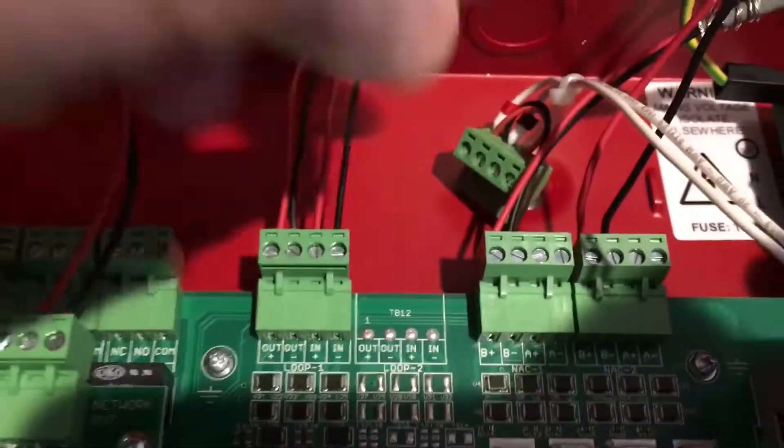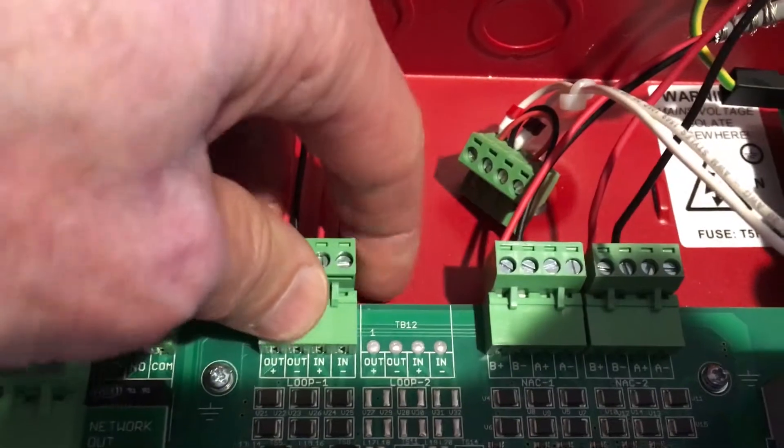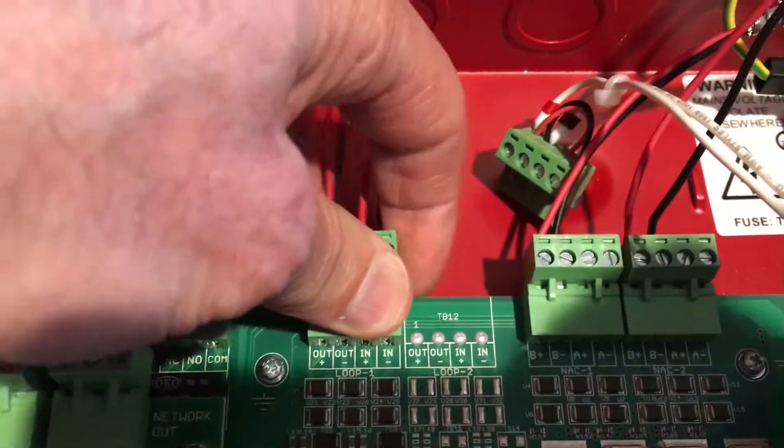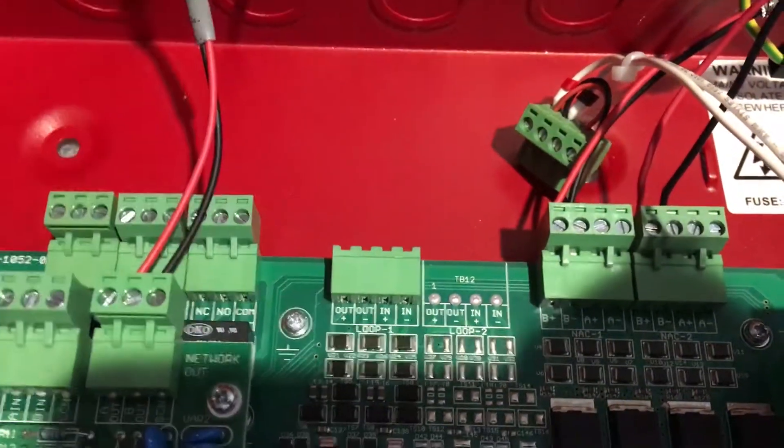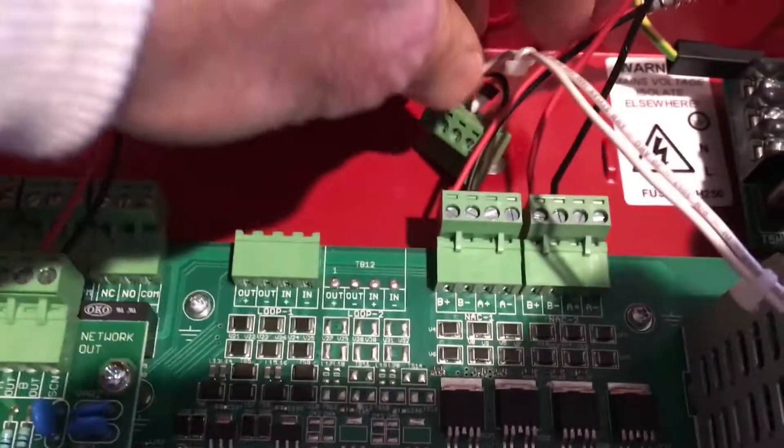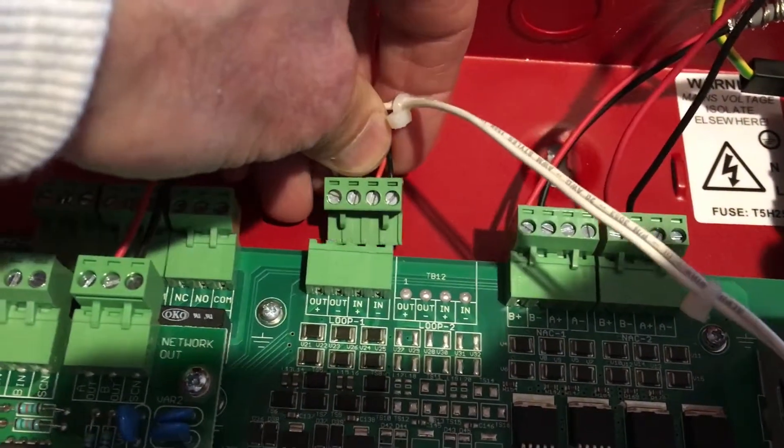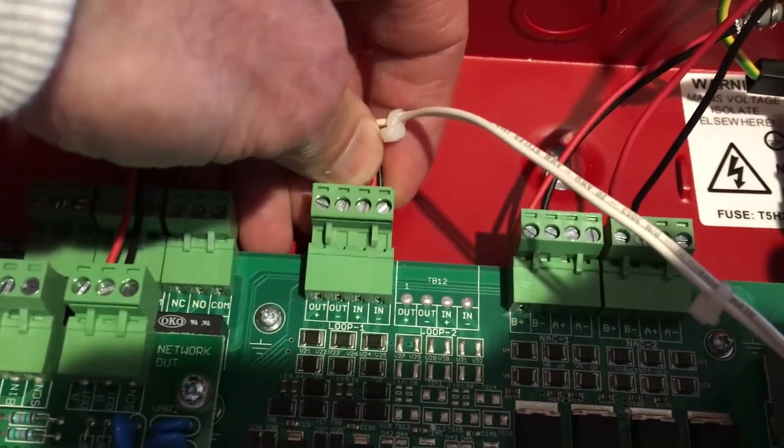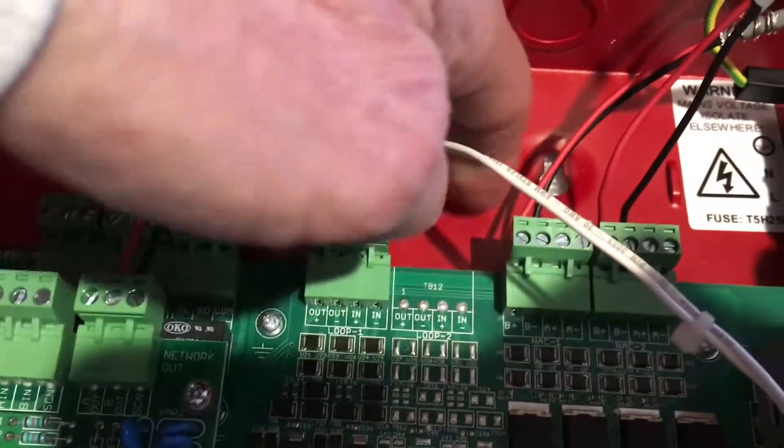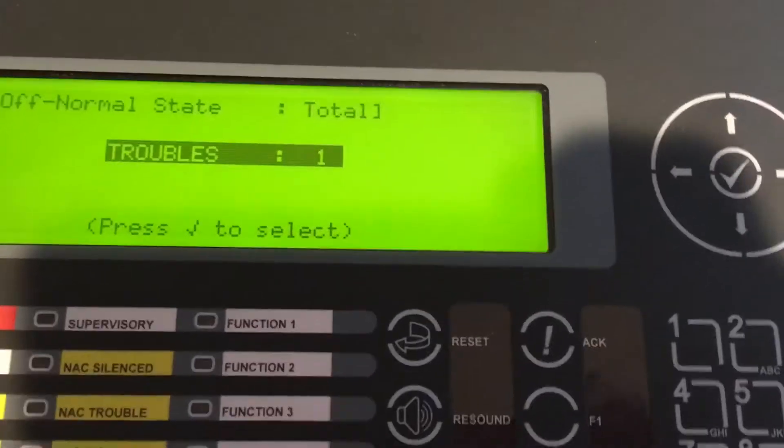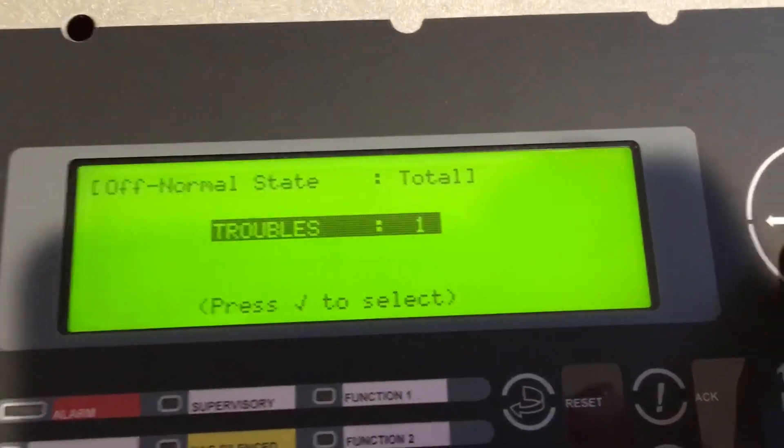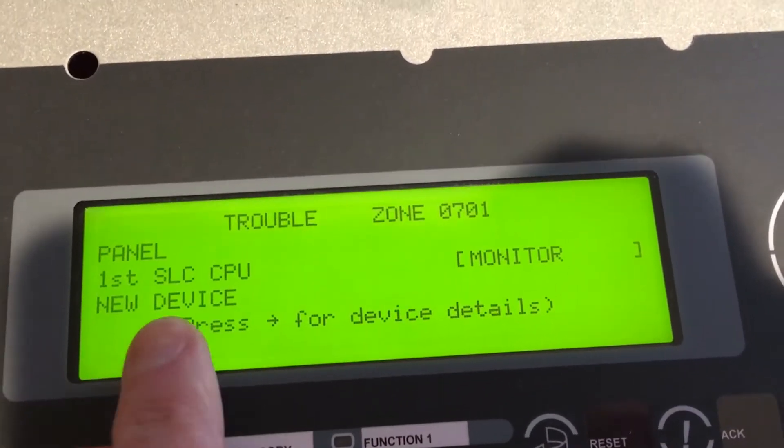Down inside of our fire panel we have our SLC circuit dummied out. What we'll do is remove that dummy wiring and here's our new set of wires we're going to plug in. Notice that the panel is in trouble. Our panel did go into trouble, we'll hit the check mark over here and we'll notice that there are some new devices found in the system.